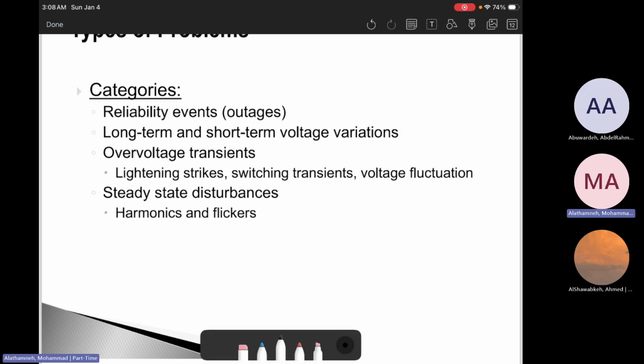lightning is a real concern in winter storms. Switching events occur with capacitor banks and network reconfiguration, especially if there is a power outage and the power is reconnected, or if there is a recloser turning off sectionalizers. Harmonics are rising due to LED drivers, chargers, and variable frequency drives. Flickers can appear in areas with large fluctuating loads, such as welders, crushers, and big motors cycling.